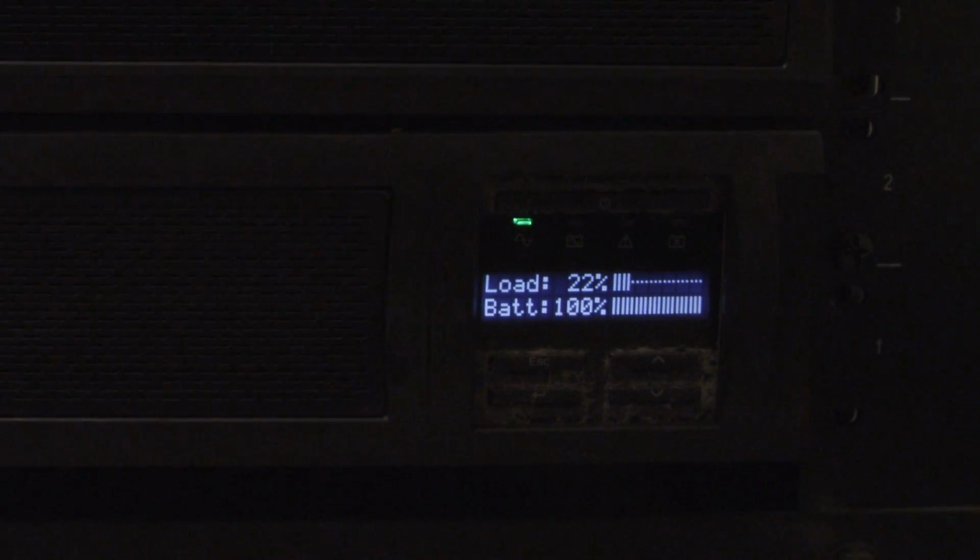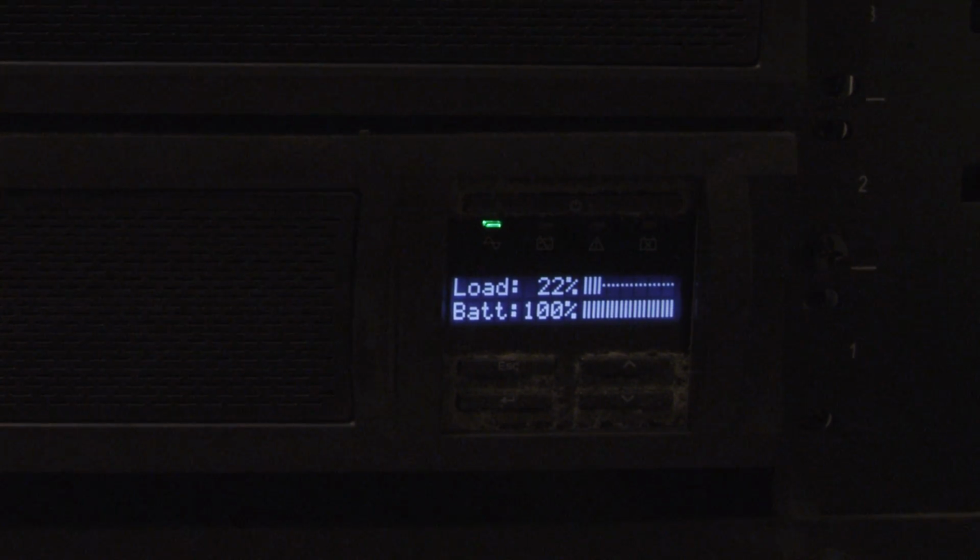Before leaving this IDF, we should discuss some environmental requirements of the room. Network equipment generates a certain amount of heat, so it's important when designing a wiring closet that we make sure sufficient air conditioning will be provided. We must also be able to continue running the network for at least some period of time during a power outage. This means that we must install uninterruptible power supplies, UPSs, to provide power to our IDF equipment.